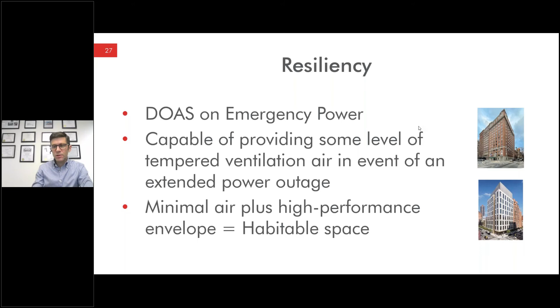This is a graph of something we looked at for Weill Cornell. We did a series of different options where we could supply 70 degree air, the normal neutral condition from outside air. We looked at heating it to 80 degrees at the unit to get more heat out of it, and then different alternatives in the envelope. We ended up with something between the gray and orange options, where we're able to maintain at least 60 degrees all year in a typical year during a power outage.